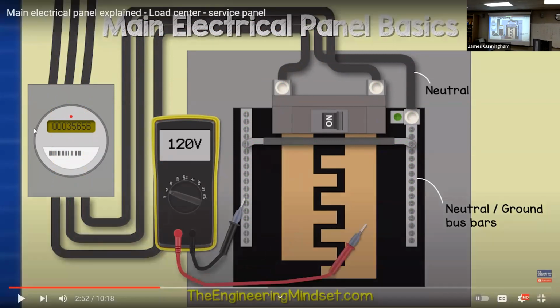Southern California Edison is required to supply us electricity that's within 5% of 120 volts. So if I test, like at one client's house, we tested it, it was 119.5 or something. It was really close to 120 volts. And we had to replace a panel in Hope Ranch and run a whole new underground service and everything. They had the wires coming from one power pole and they had a buried cable. So back in the day, they would allow you to run just a buried cable. It was an insulated cable. It was meant to go in the ground, but not in conduit.